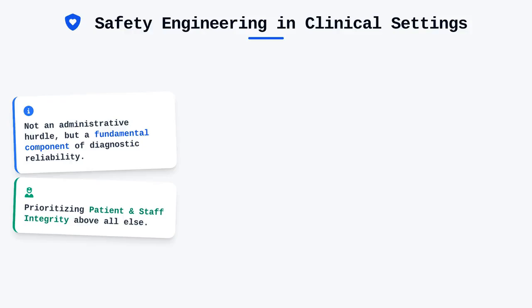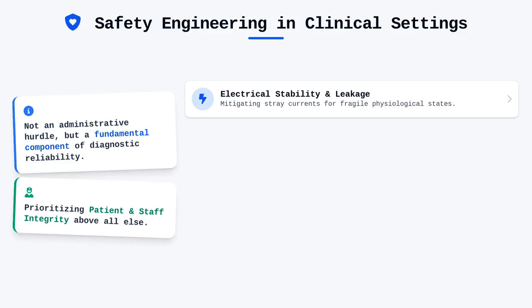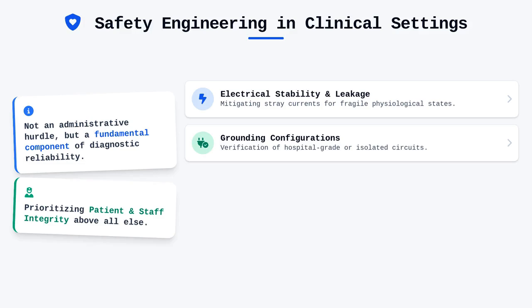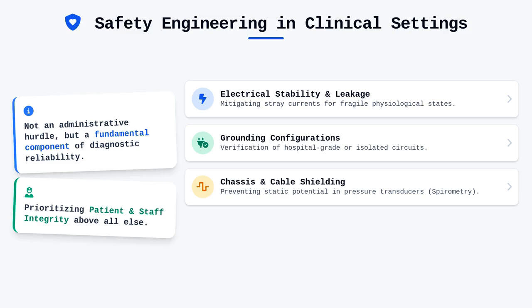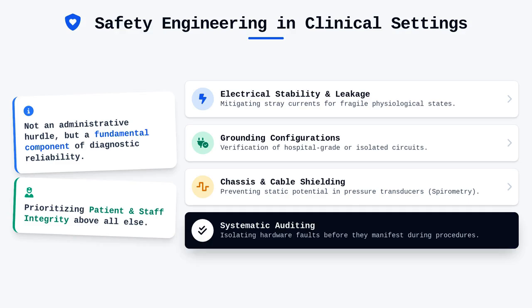When we examine diagnostic hardware, our primary concern involves the electrical and mechanical stability of the equipment before it ever touches a patient. Electrical leakage is a significant risk factor in any environment where conductive leads and sensors are attached to a subject who might be in a fragile physiological state. Grounding configurations represent the first line of defense against these stray currents, and you must verify that all instrumentation is connected to a hospital-grade or dedicated isolated circuit. Regularly assessing the integrity of the chassis and the shielding of the cables prevents accumulation of static potential, which could otherwise interfere with the sensitive pressure transducers used in plethysmography or spirometry. By systematically auditing these systems for structural faults, you isolate the hardware from potential failure points long before they manifest during an active procedure.